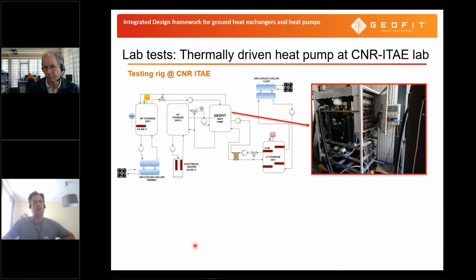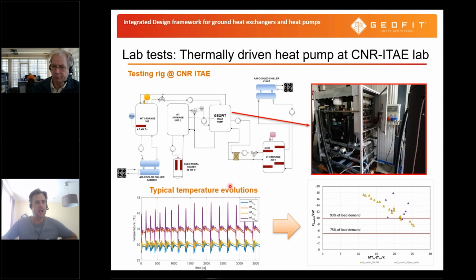In the same way, there have been lab tests done by the colleagues from CNR in Messina, Sicily, with the prototype of the thermally driven heat pump. The thermally driven heat pump was tested, as you can see here, under those typical temperature evolutions. It is not a constant operation. Yeah? It's more a batch operation with desorbing, adsorbing the water in the solid. That's a type of zeolite. So it's a more complex system than the electrically driven heat pump. They did exhaustive testing in order to optimize the system and also find the proper operating conditions for the integration afterwards in the pilots. Yeah?